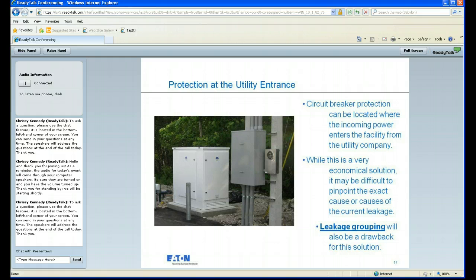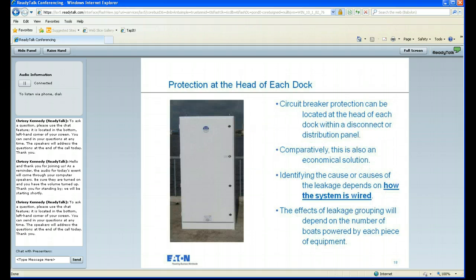Leakage grouping, which we'll go into a little more detail in a couple of slides, will also be a drawback. Leakage grouping basically occurs when there are multiple boats causing leakage into the water. They may be providing small amounts, but if you add all of them together, that's what's causing a circuit breaker to trip or there to be problems within the marina.